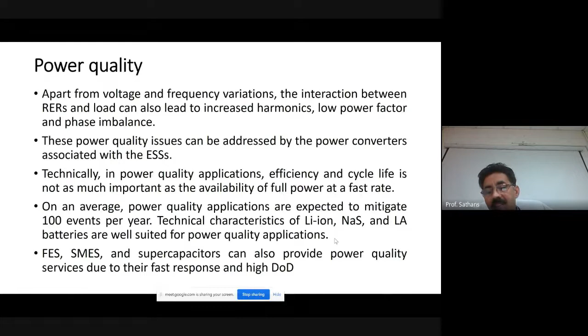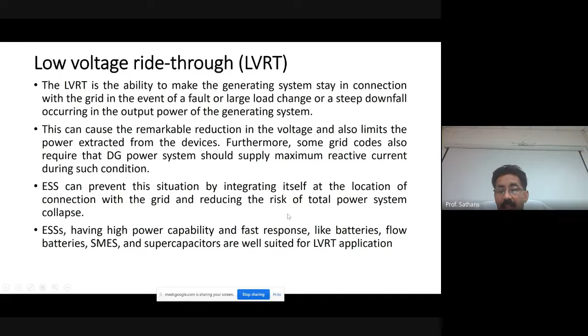Low voltage ride through applications: that's the ability to make the generating system stay in connection with the grid in the event of a fault, or large load change, or steep downfall occurring in the output power of the generating system. In case that happens, your generating system should still be able to stay connected to the grid without causing a collapse. So in those kinds of applications, a good amount of support can come through the renewable energy sources. In such conditions, they can be integrated at the location of connection with the grid, reducing the risk of total power system collapse.